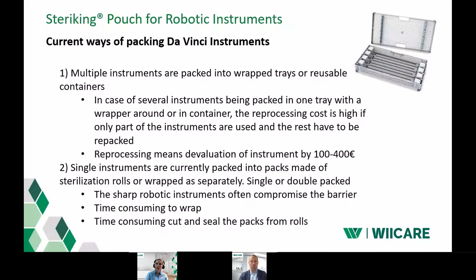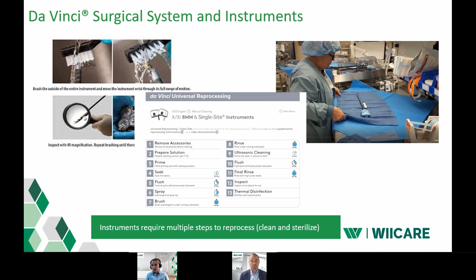And then the second method is that the robotic instrument would be wrapped one by one in sterilization wrap or pouch cut and sealed from a roll. This can be also done as a single or double packaging. But this method is quite time-consuming, and there is a risk that the instrument can cut and compromise the barrier of the sterile packaging. So we want to highlight also that the robotic instrument can be reprocessed only a limited number of times. Here is to show that the instruments are undergoing a deep cleaning procedure in many steps before the sterilization and packaging.